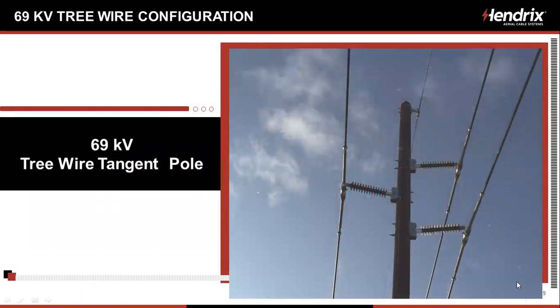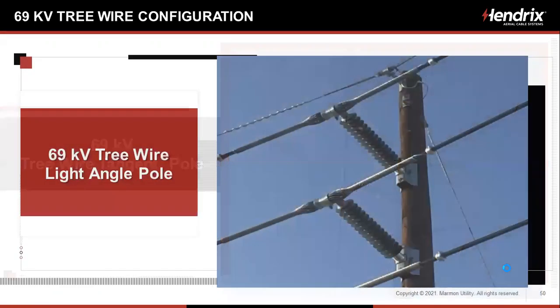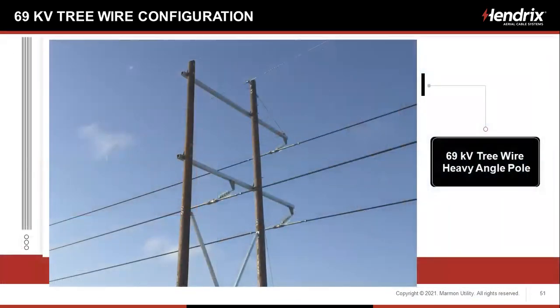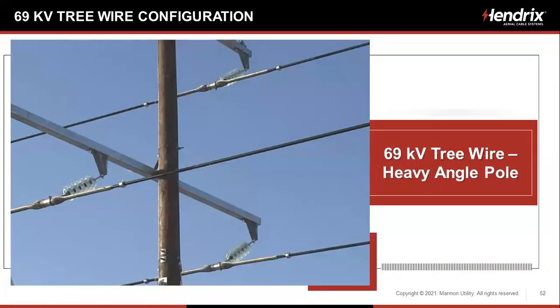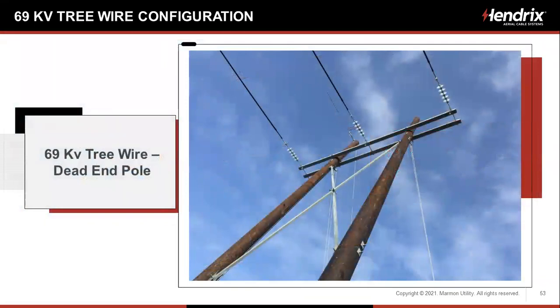Here it is on line post insulators with suspension clamps covering the covered conductor. And we can talk a little bit more about this offline, if you will, but that's a tangent pole. Here's a light angle pole, again using the line post insulators for standoffs. Here's a heavy angle pole using suspension insulators with the same IPC connectors. And here's a close-up of the heavy angle pole and the 69 kV dead end.